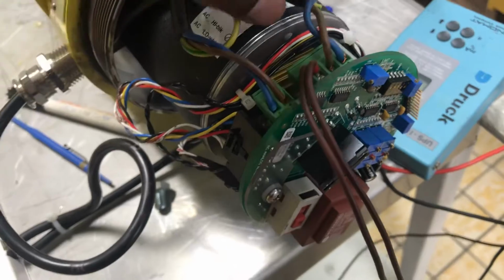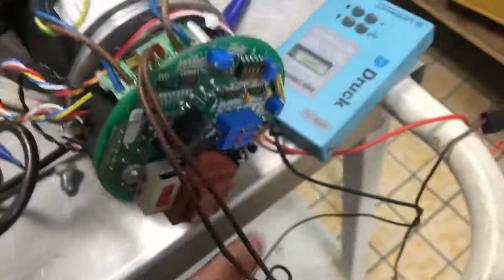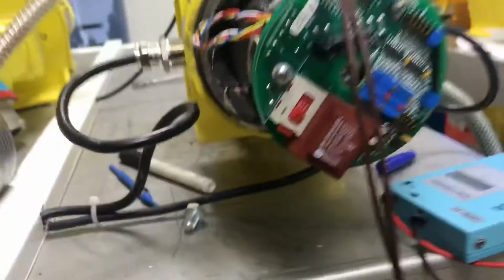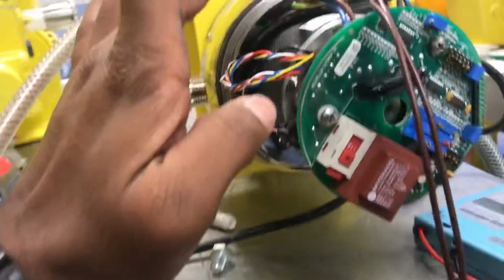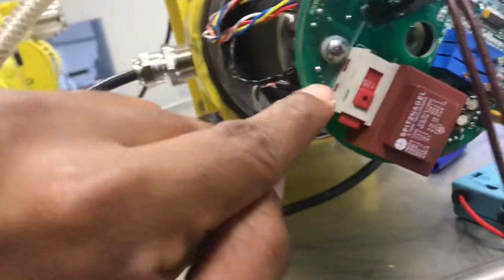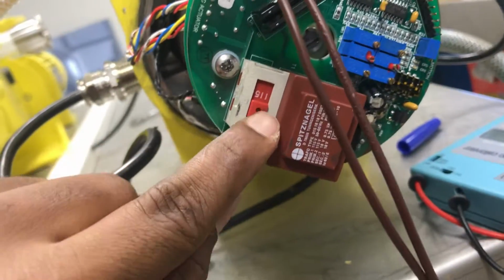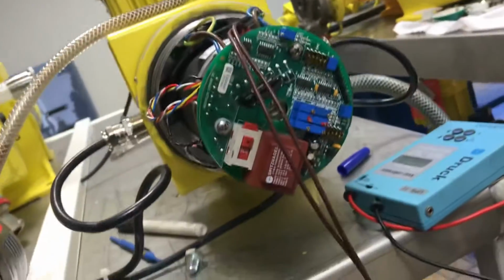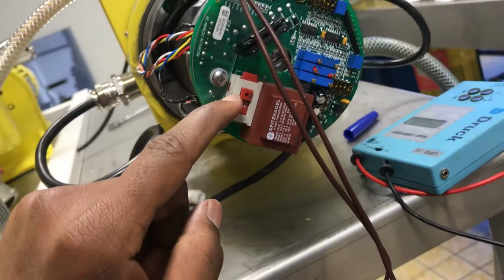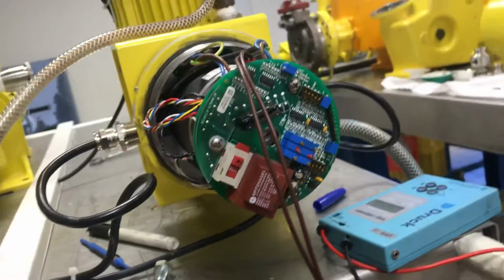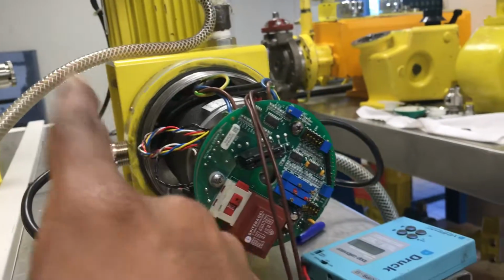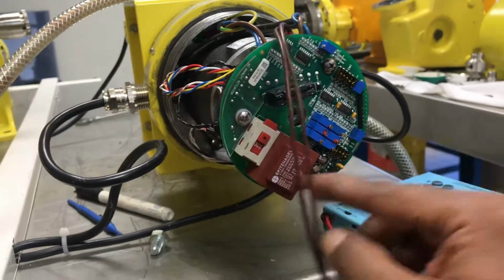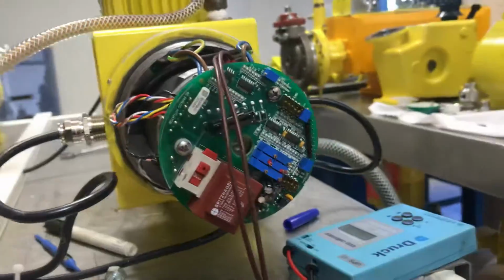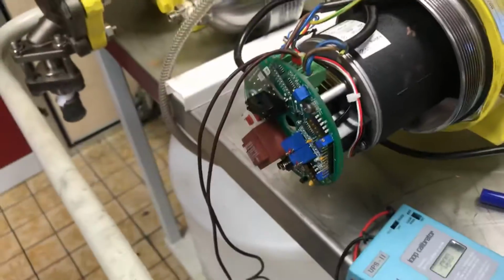This is a power cable, this is a signal cable 4 to 20 milliamps, this is a feedback cable, and this is the dip switch. Now before turning on the power, you have to check this dip switch whether it is 115 volt or 230 volt. Here we are using 230 volt, and mostly in UAE also it's 230 volt. So once you give the 230 volt, you have to ensure, because if you are giving 230 volt and here it's 115, then the transformer will burn. So make sure, ensure it twice.